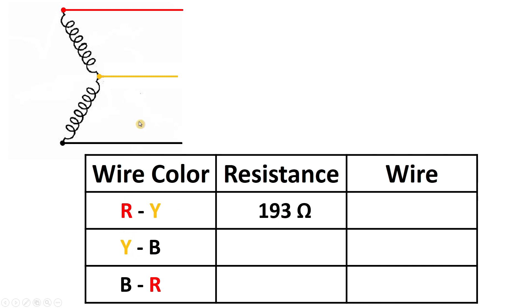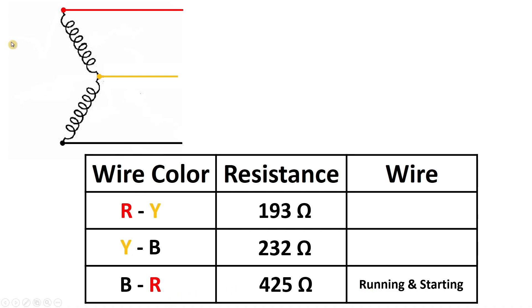Now between yellow wire and black wire I will measure resistance — I assumed 232 ohms. After this, between black wire and red wire I got 425 ohm resistance. In these values you just have to see between which two wires you are getting the highest resistance. You can see between red wire and black wire we got the highest resistance. This means these two wires are of the starting and running winding. The third wire — the one left out — is the common wire.